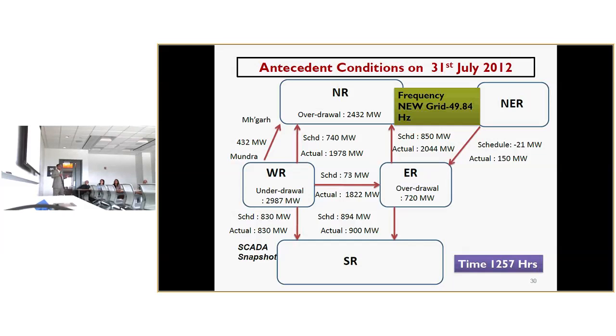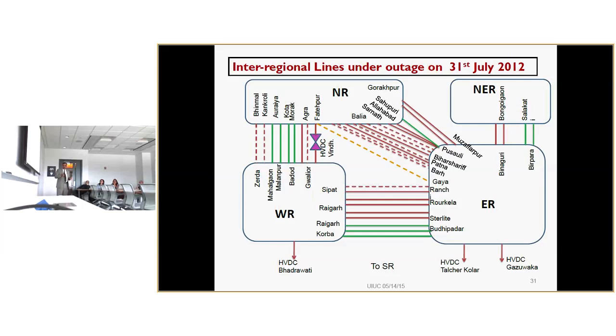They did not know what had really happened on the first day when they restored. They had no way to check. Well, they actually checked the relay. It had operated, they reset it. They didn't find any fault, so they synchronized all the regions again. But there was some difference on that day. The difference was that when they resynchronized, some of the loads also got reduced.